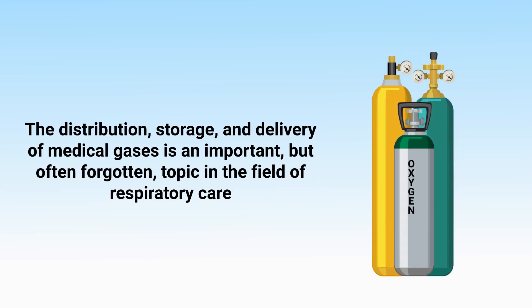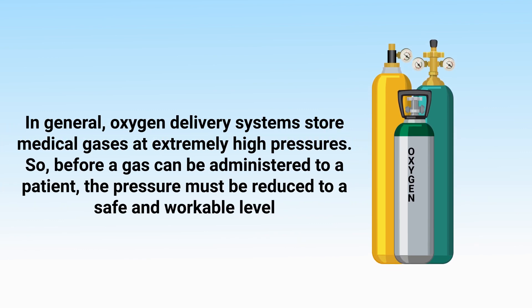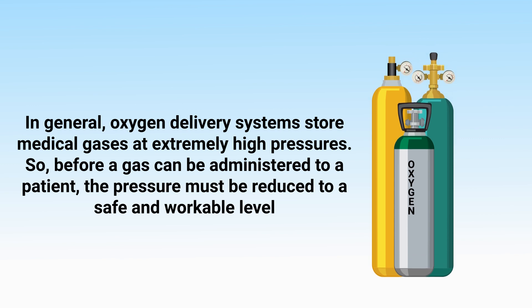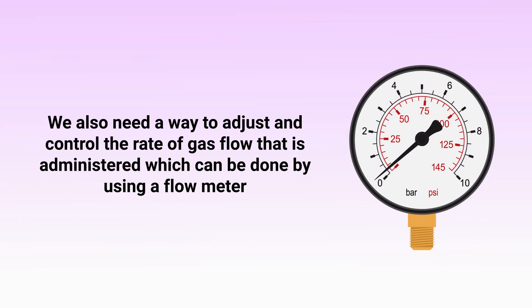The distribution, storage, and delivery of medical gases is an important but often forgotten topic in the field of respiratory care. In general, oxygen delivery systems store medical gases at extremely high pressures, so before a gas can be administered to a patient, the pressure must be reduced to a safe and workable level. We also need a way to adjust and control the rate of gas flow that is administered, which can be done by using a flow meter.